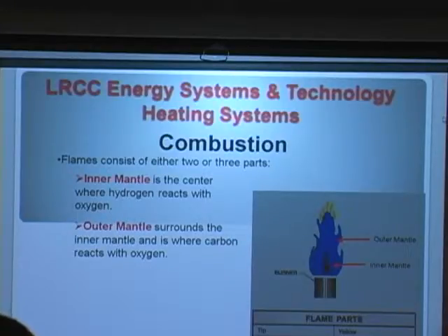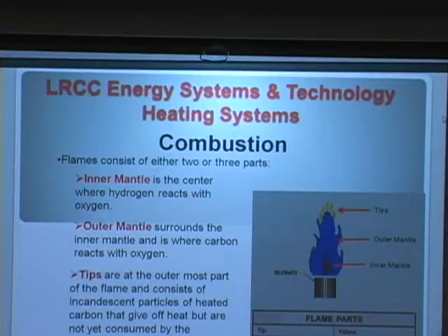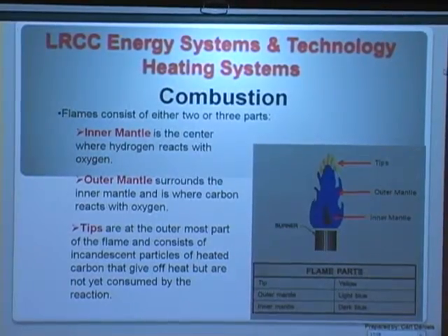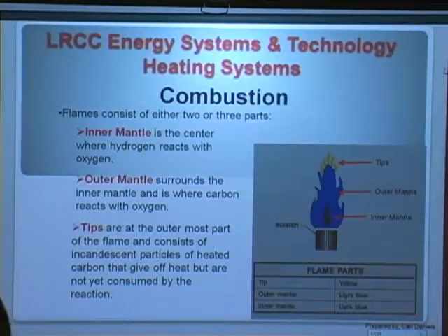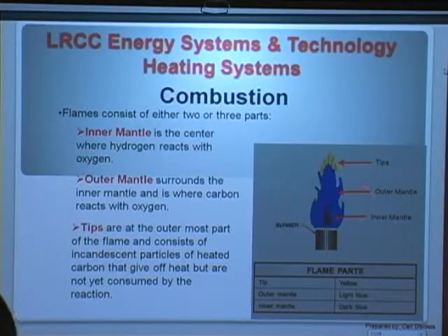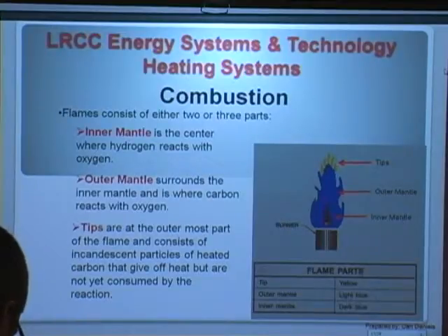When you're looking at a natural gas flame, you'll see the center — the heart of the flame — is deep dark blue. Then you'll have a lighter blue flame surrounding it. Then you'll have the outer tips at the very top that flash off in a little bit of yellow — that's the unburned particles of carbon that have made it through the reaction untouched. Your yellow tips don't give off much heat. Your inner mantle has the largest source of heat, your outer mantle the next largest, and your tips the least.